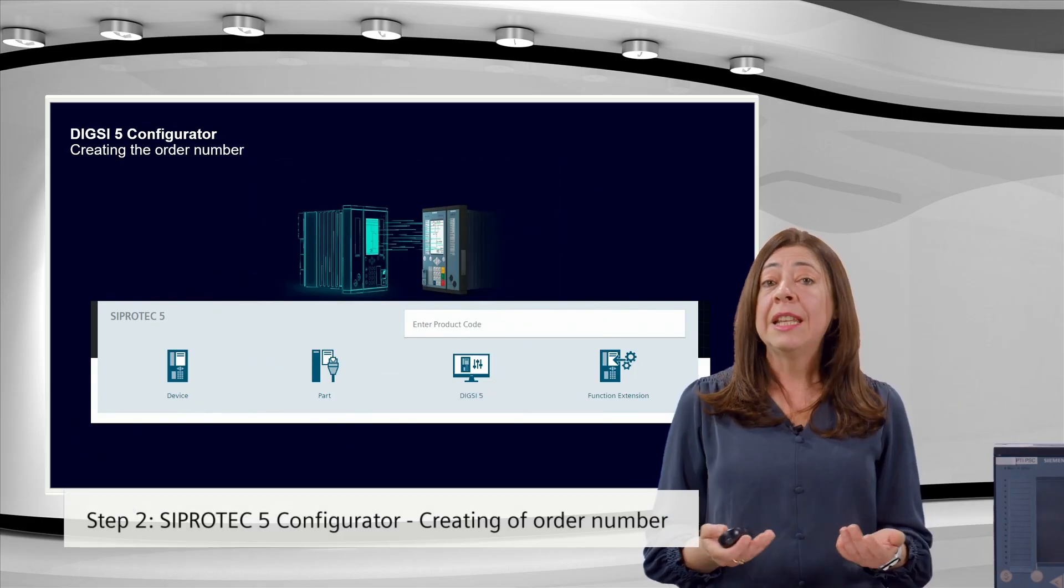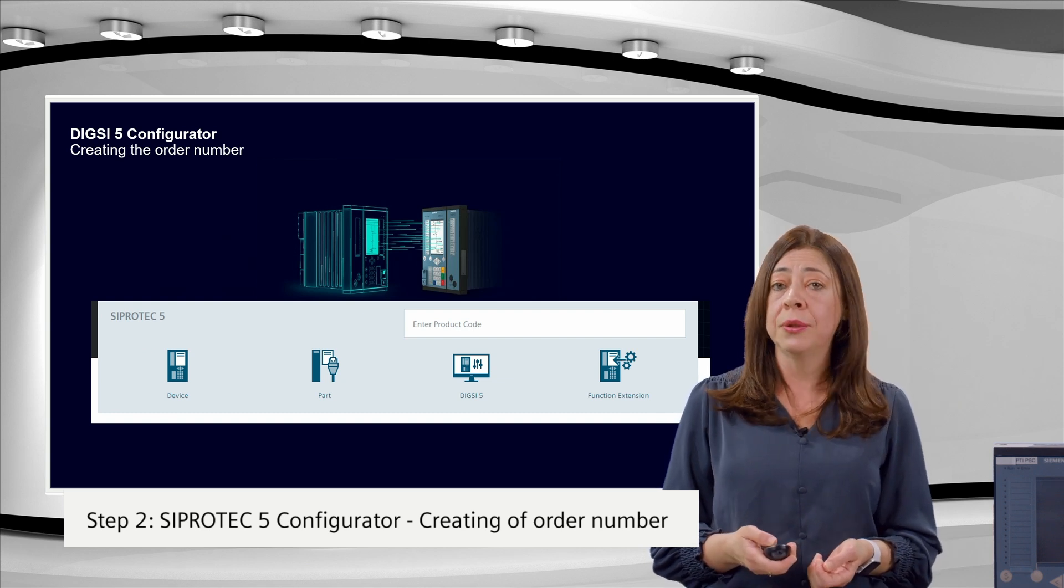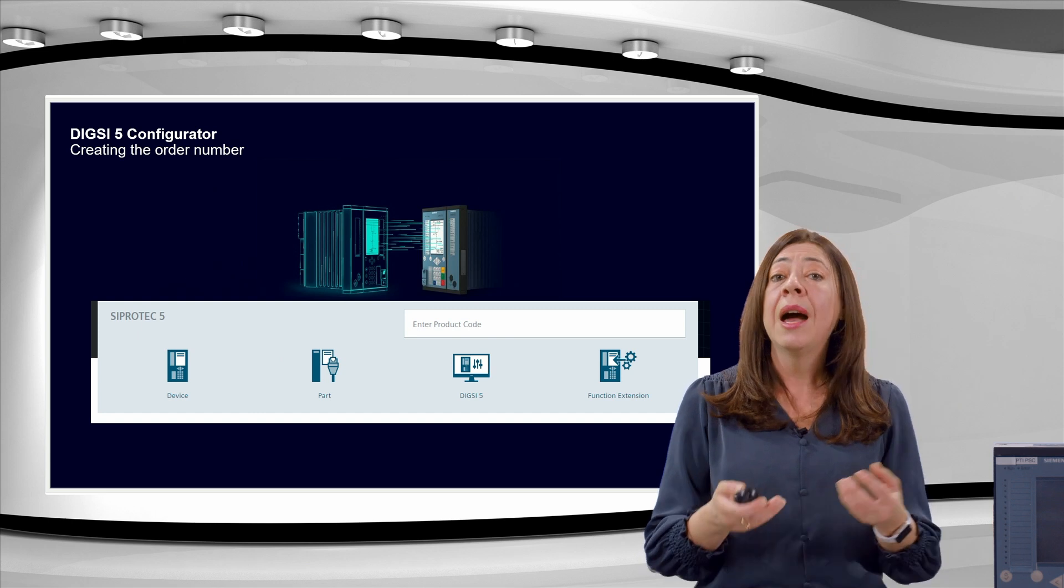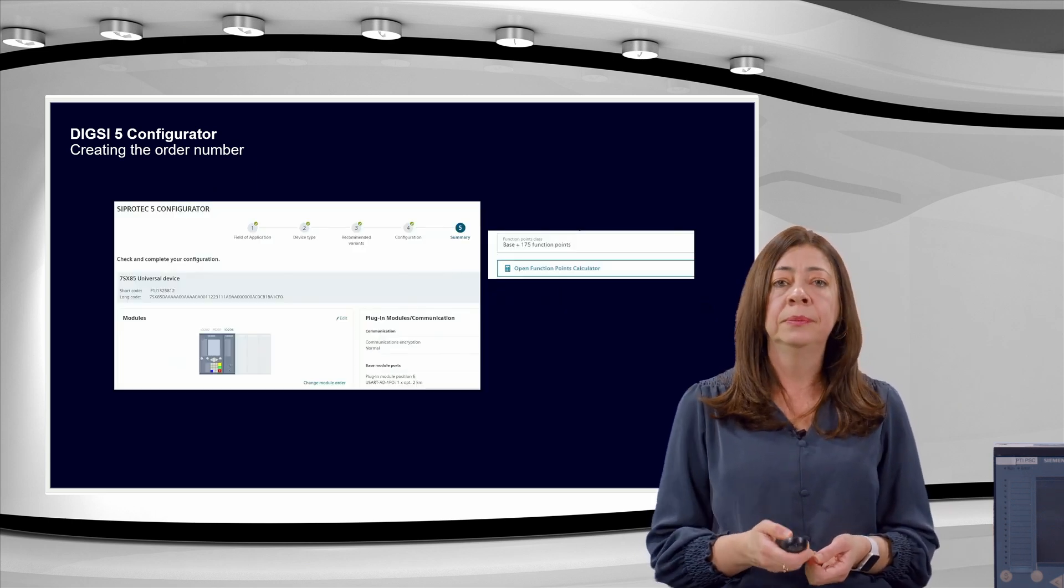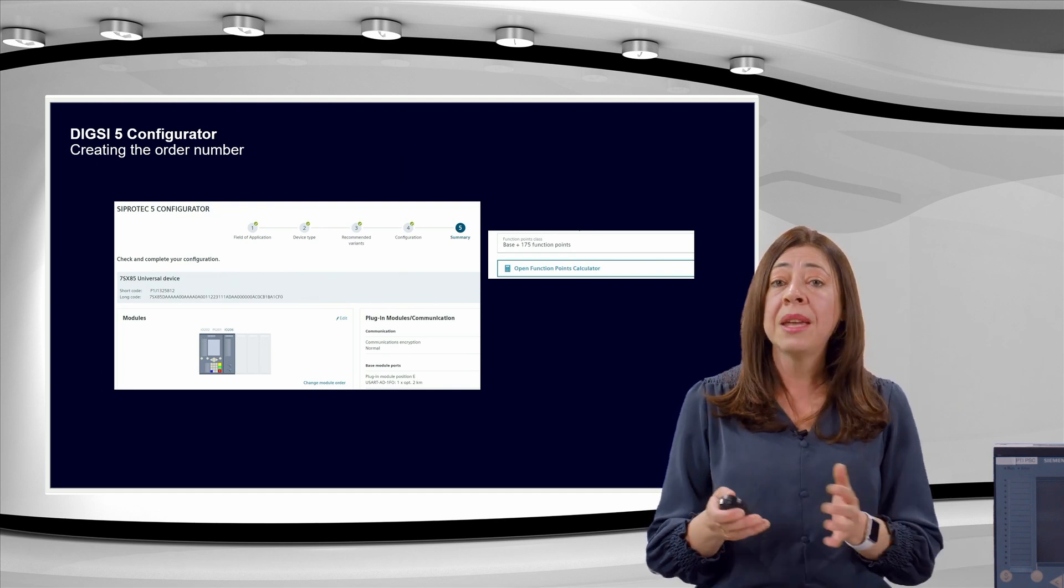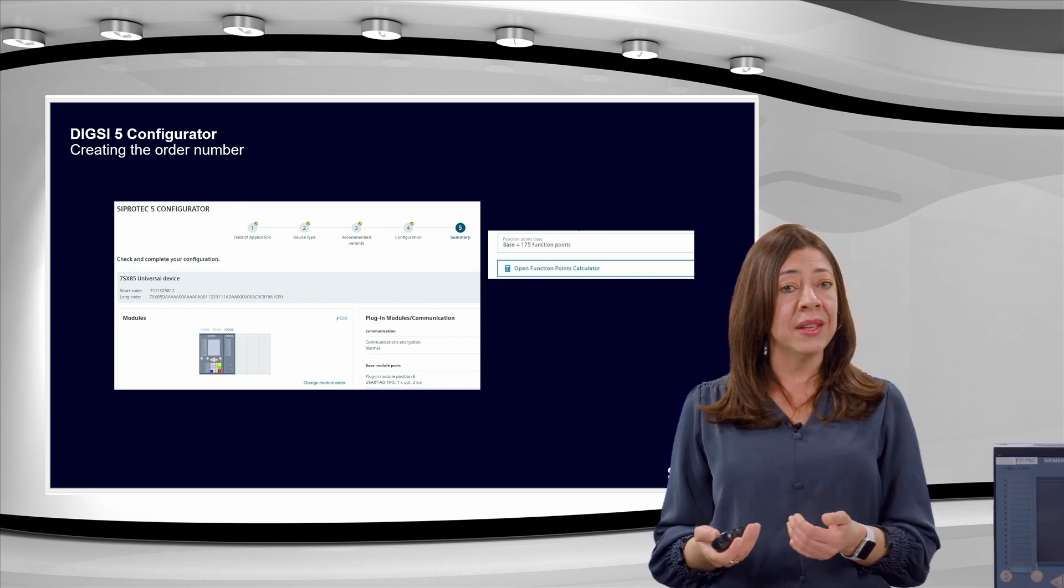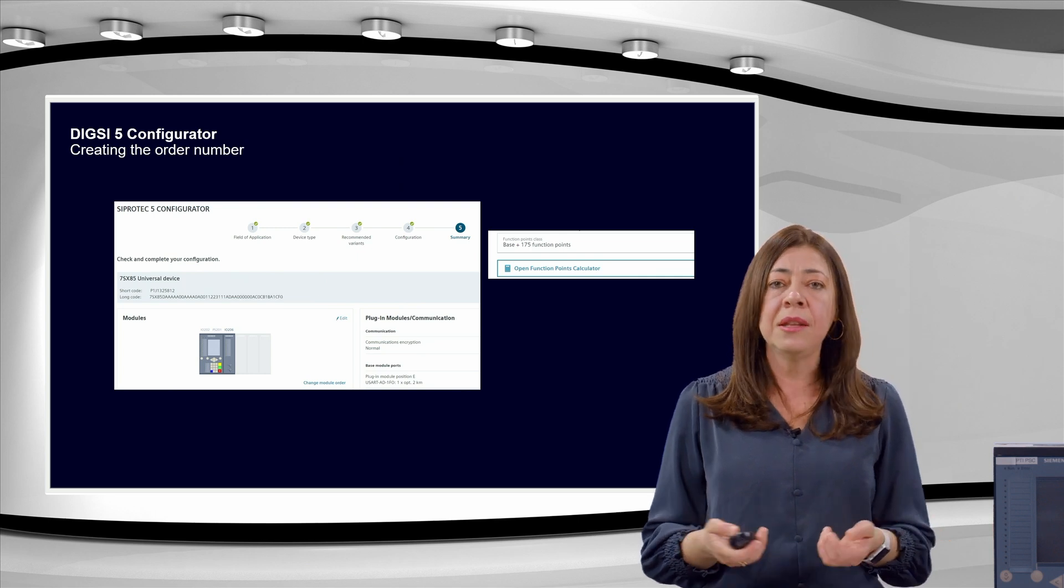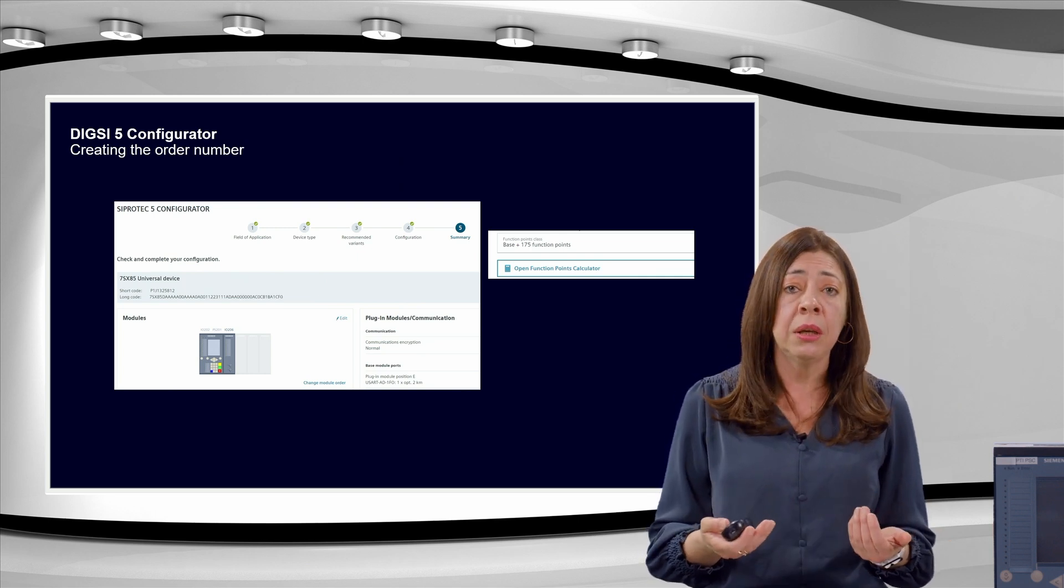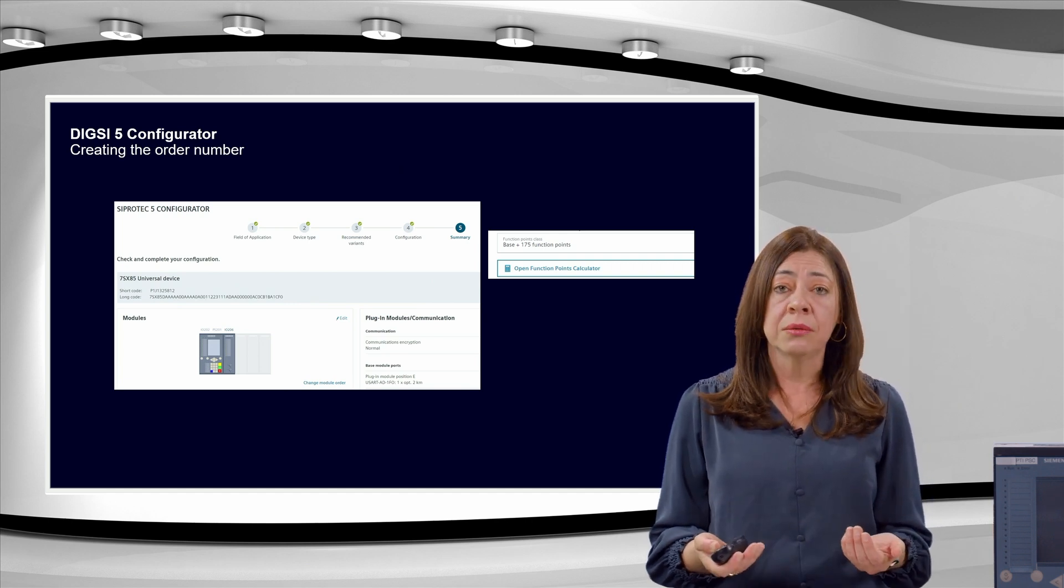In the next step, we can make use of the SIPROTEC 5 configurator to define the specific hardware to be used and the required amount of function points. Remember to include all the functionality you are looking for with the migration. And also check if you want to take advantage of new features which are useful and can be easily added in the device, such as circuit breaker monitoring, power quality, or automatic voltage regulation.